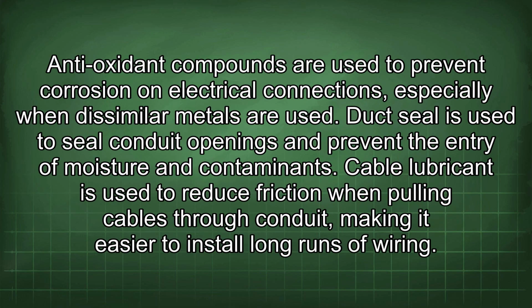Antioxidant compounds are used to prevent corrosion on electrical connections, especially when dissimilar metals are used. Duct seal is used to seal conduit openings and prevent the entry of moisture and contaminants. Cable lubricant is used to reduce friction when pulling cables through conduit, making it easier to install long runs of wiring.